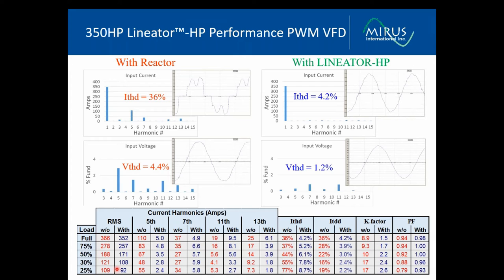4.9. You can see, as we go down in lighter loads, similar levels of reduction on all the harmonics. Current distortion dropped significantly. Total demand distortion, which is an IEEE 519 definition for levels of harmonic mitigation required. And as we go into lighter loads, we can see we're well below the 5% on TDD. We reduce K factor, which is a measure of the heat content in the harmonics and the nonlinear loads, and we improve power factor. You can see the resultant power factor, even at light loads, very, very high power factor levels.